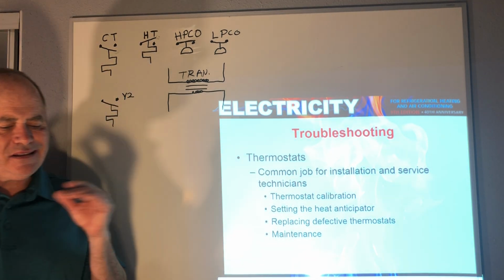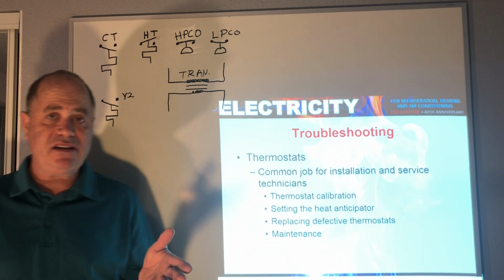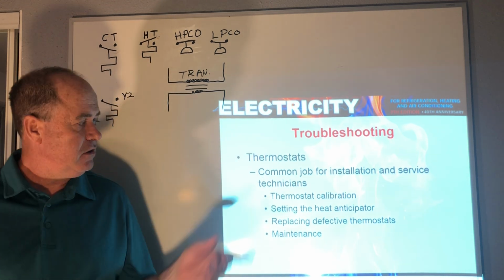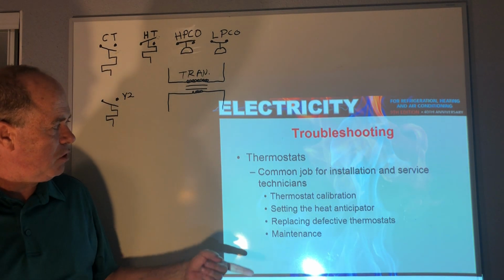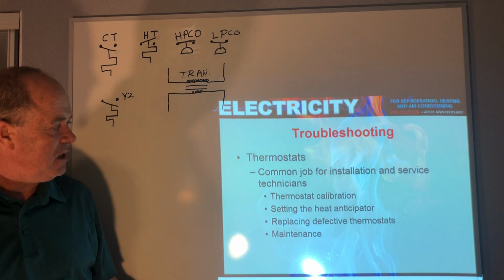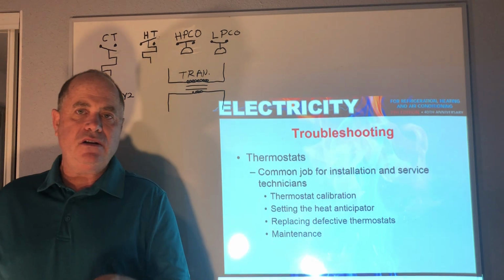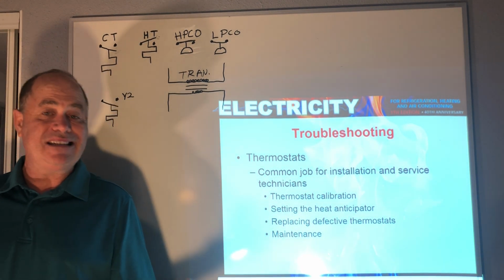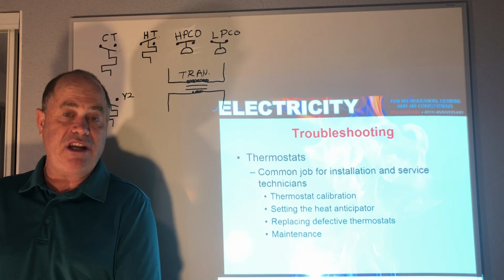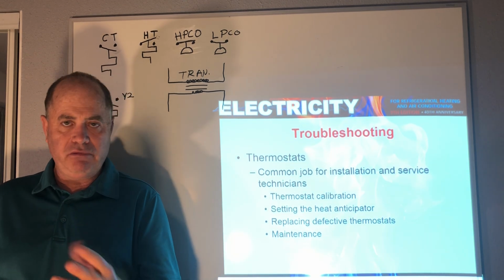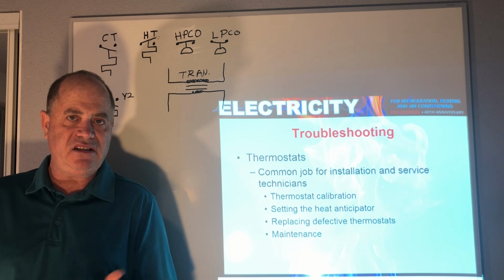Now, on troubleshooting thermostats, we talked for a little bit about it. The commentary here is a little bit more about installation. If the thermostat is getting power but not passing it through when it should, then really the thermostat's at fault and it needs to be replaced.